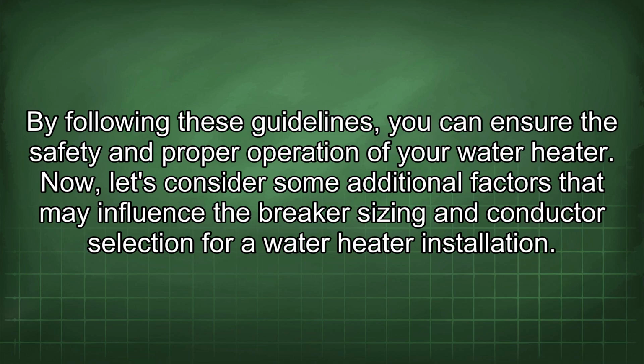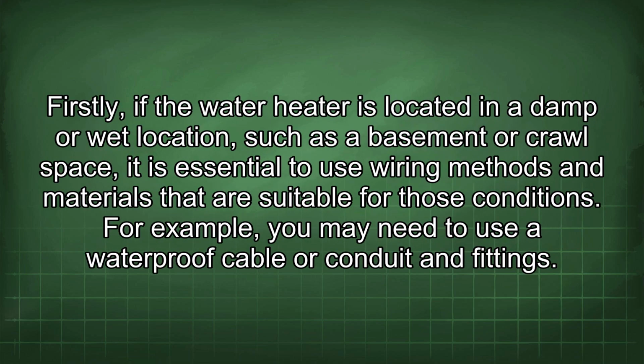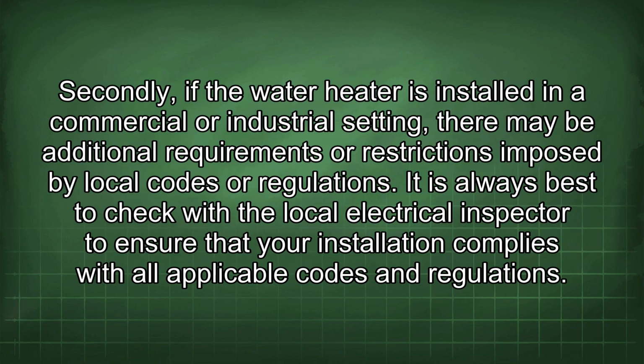Now let's consider some additional factors that may influence the breaker sizing and conductor selection for a water heater installation. Firstly, if the water heater is located in a damp or wet location, such as a basement or crawl space, it is essential to use wiring methods and materials that are suitable for those conditions. For example, you may need to use a waterproof cable or conduit and fittings. Secondly, if the water heater is installed in a commercial or industrial setting, there may be additional requirements or restrictions imposed by local codes or regulations. It is always best to check with the local electrical inspector to ensure that your installation complies with all applicable codes and regulations.